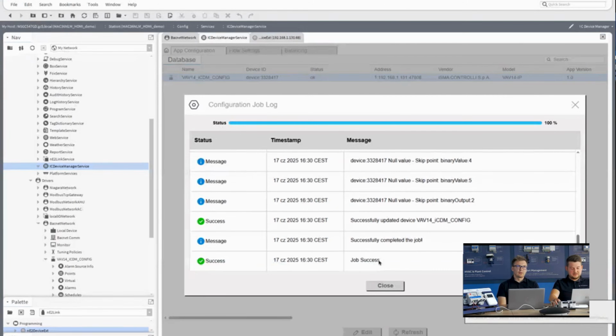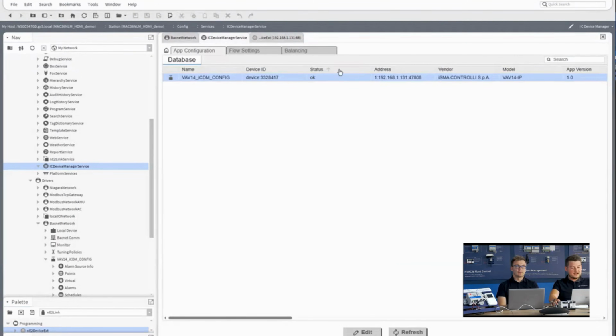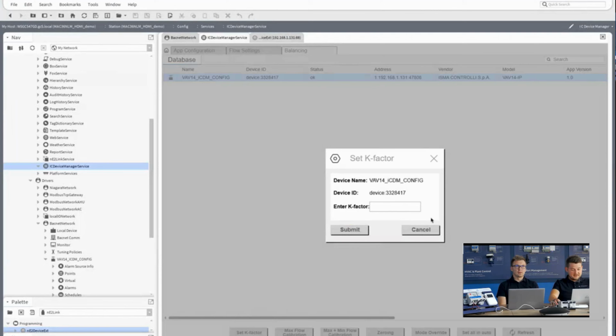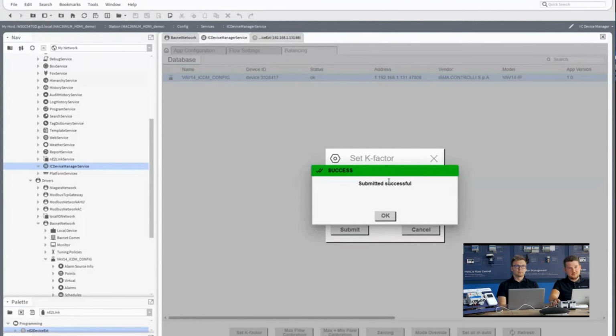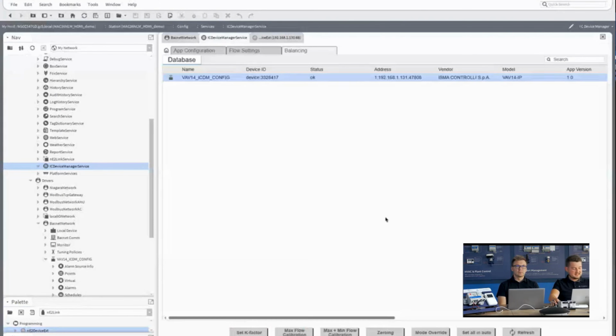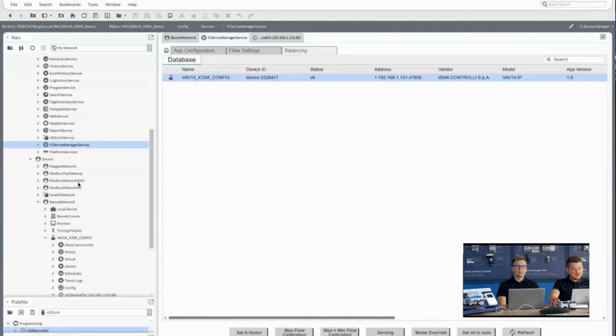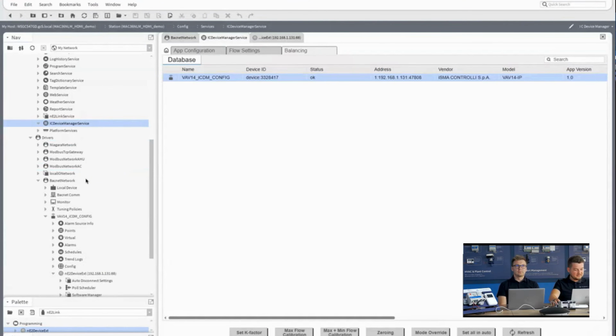So as you can see, the job succeeded. The configuration has been sent to the controller, and same for the flow settings and the balancing. So all options are here. So I can set the K factor. I can change the value right here, submit it to the controller, and I have the confirmation that the change I have done to this controller has been submitted successfully. So let's accept it. And yet this is for the configuration, but let's not forget about the programming itself.